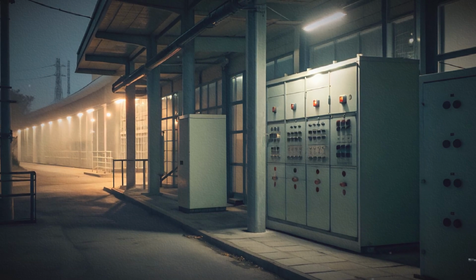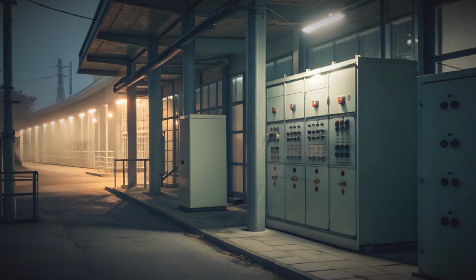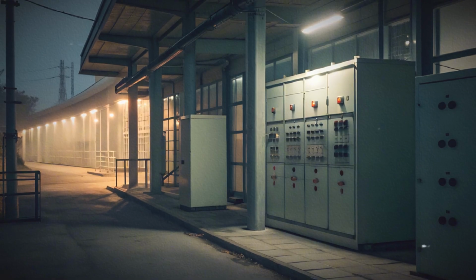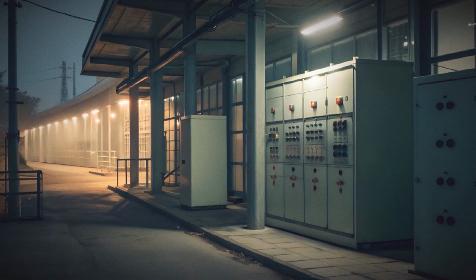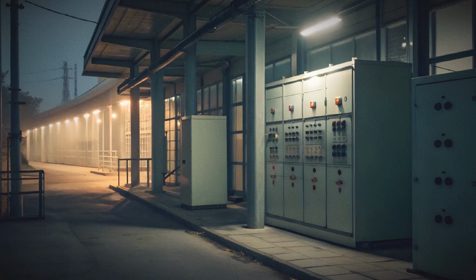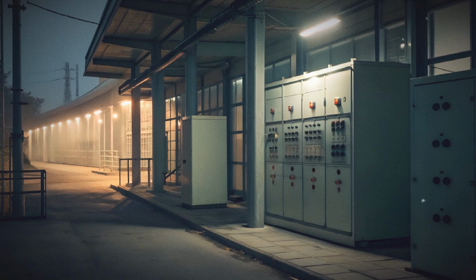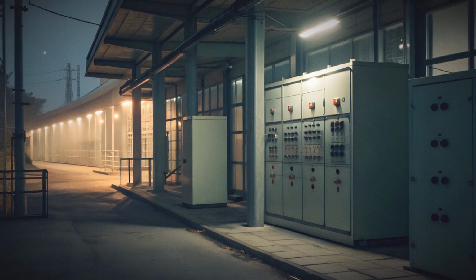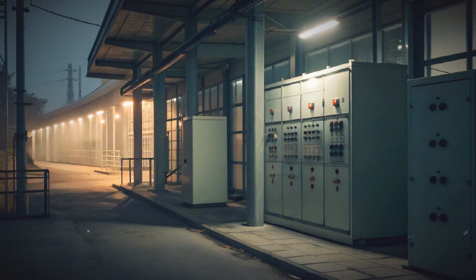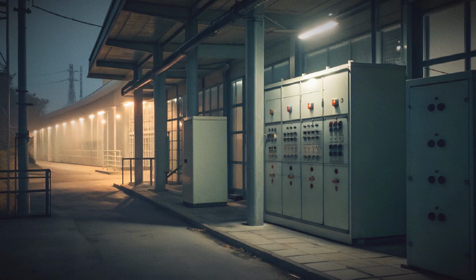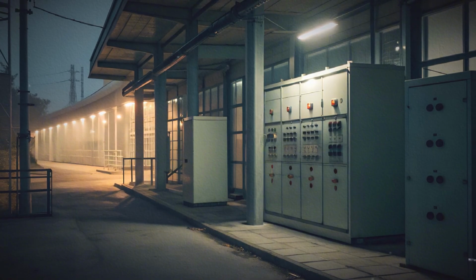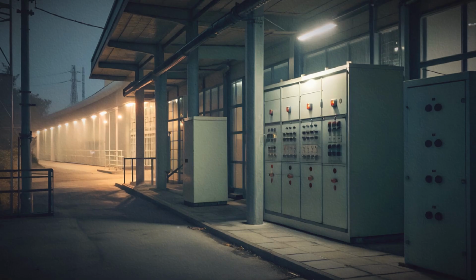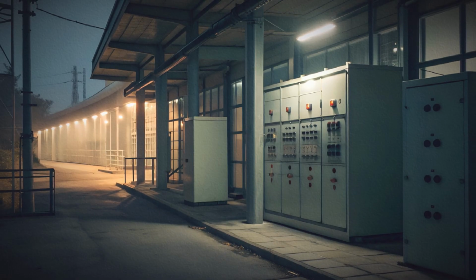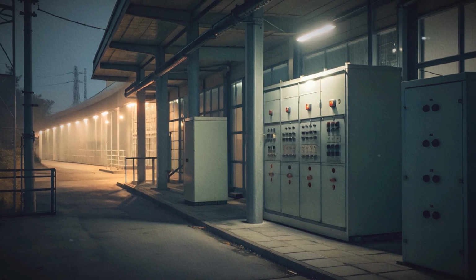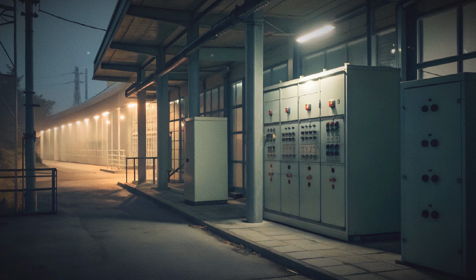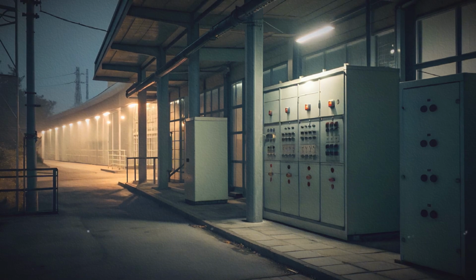Relays are decision-making devices. Some relays respond to the magnitude of current. These are often called overcurrent relays. Others detect differences between currents entering and leaving a device. These are known as differential relays. A differential relay can identify an internal fault in equipment, such as a transformer or a generator, by comparing signals from two or more locations.